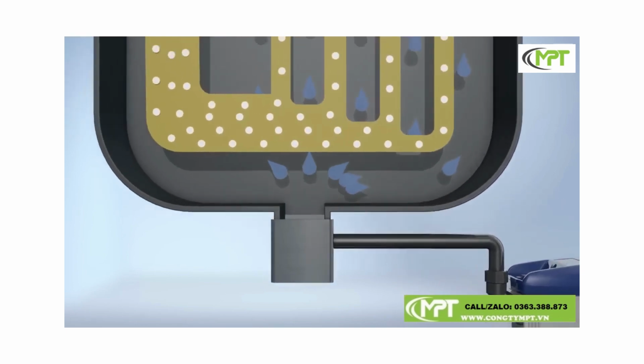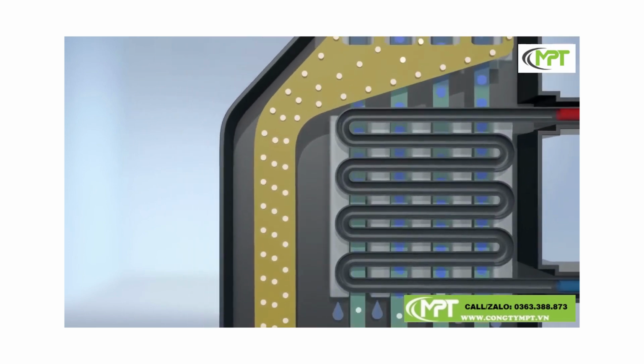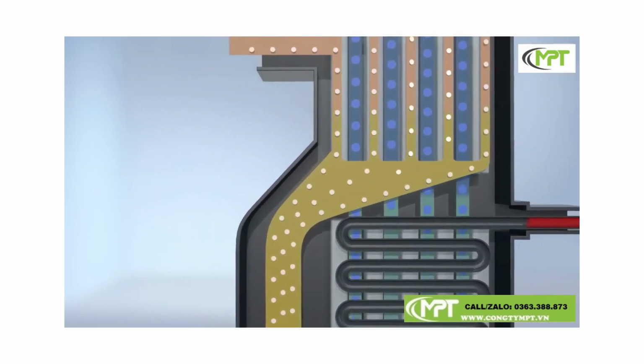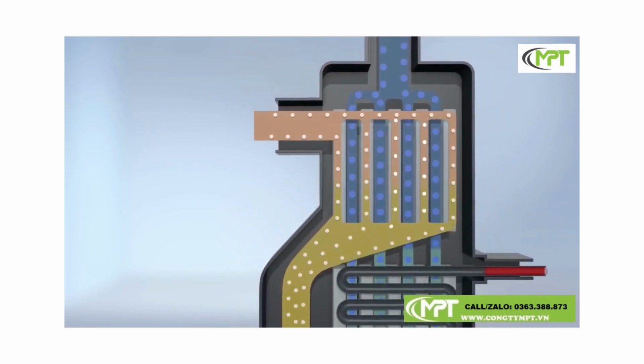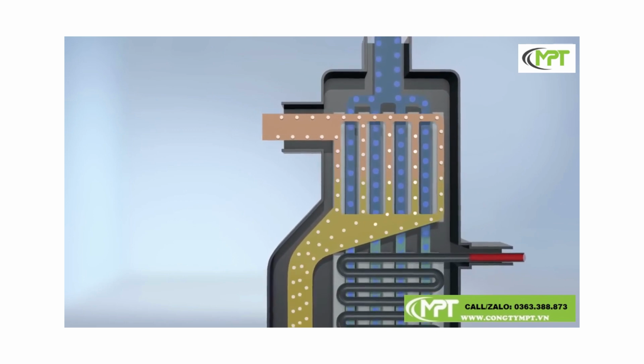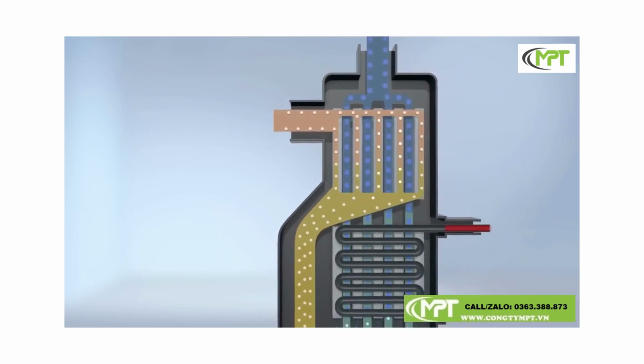The cool, dry compressed air next flows through the upper section, again past the entering air, cooling it as before in a countercurrent process, and is thereby reheated. This further reduces the relative humidity, making the air even drier.